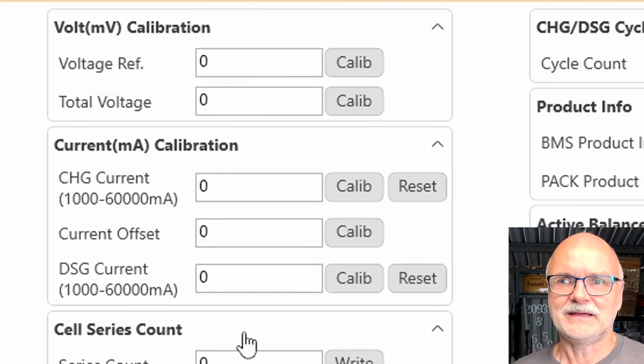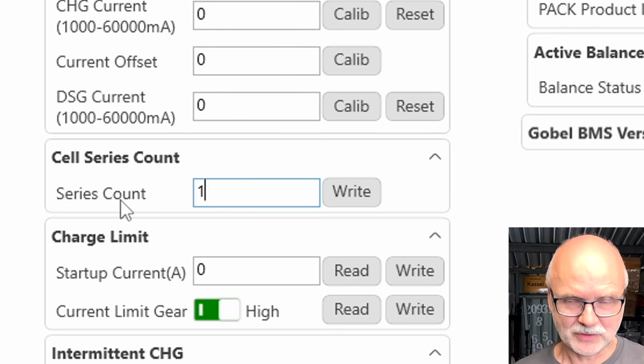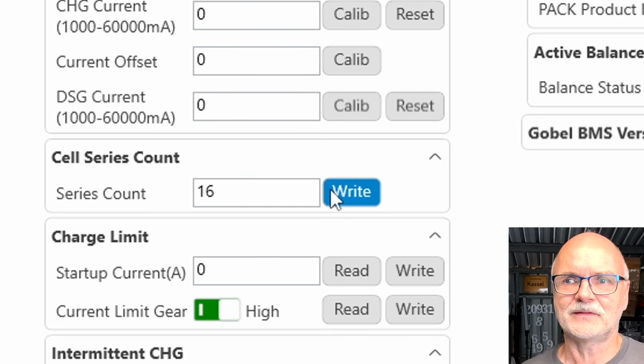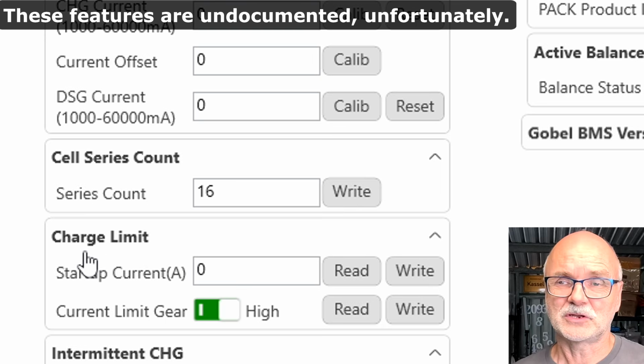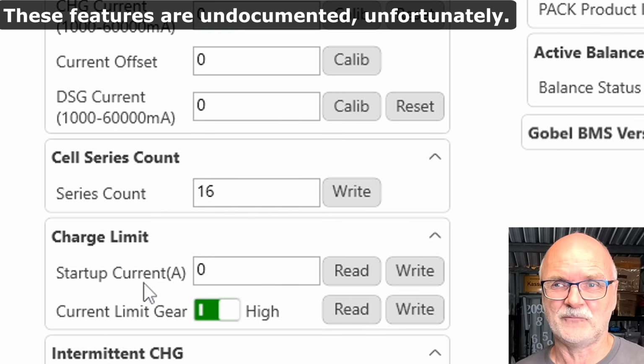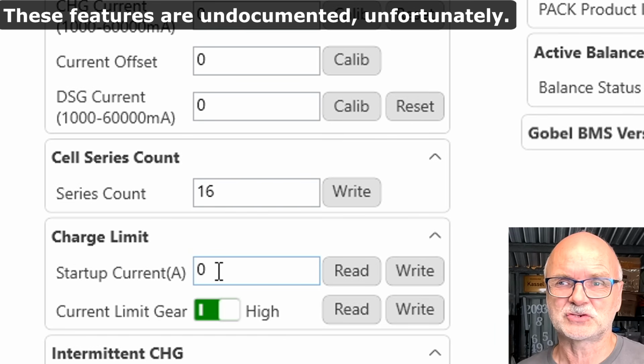But I'm not sure if we still need a calibration or even an offset for measuring the current through a BMS. Cell count, we can put in 16 and write this back to the BMS. We've got a charge limit, a start-up current, I think this is for the inrush current if you connect an inverter. So you can set a threshold here.